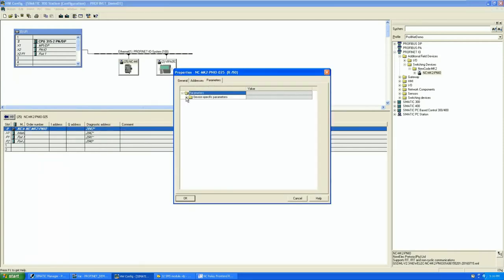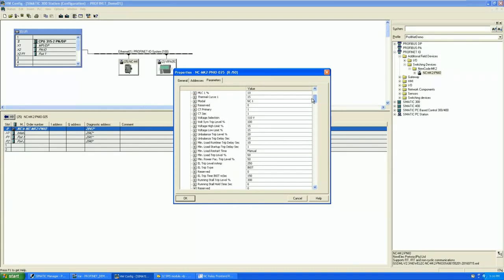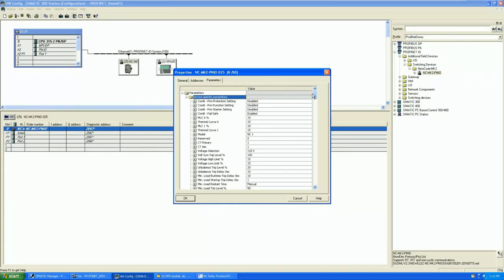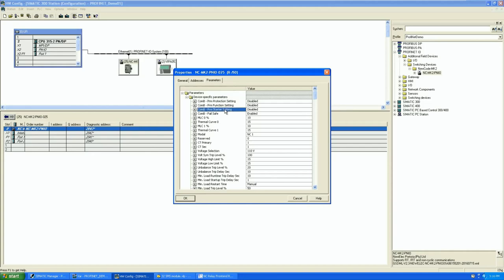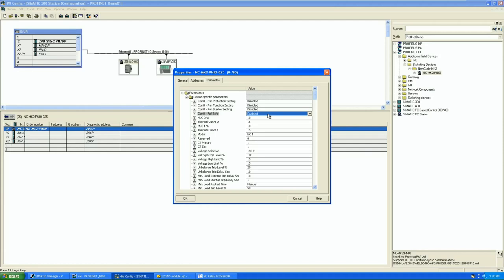Parameters can be configured by right clicking on slot 0 of the NewCode PROFINET module and selecting Object Properties. Under the Parameters tab, the parameters of the NewCode can be found. Here all the Protection, Logic, and Starter Logic settings of the NewCode relay can be configured, but the Protection, Function, and Starter needs to be enabled in order to download these configurations. A Failsafe bit is also enabled. When the setting is enabled, the cyclic words from the PLC to the NewCode relay will be written as zeros as soon as the NewCode PROFINET module loses communication with the PLC. When disabling this feature, the NewCode relay will retain the last sent cyclic words from the PLC till a power failure or communication gets restored.